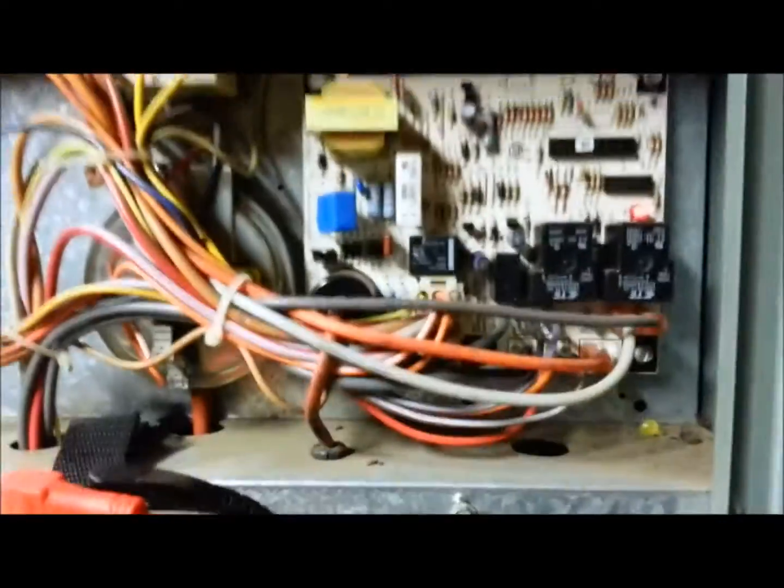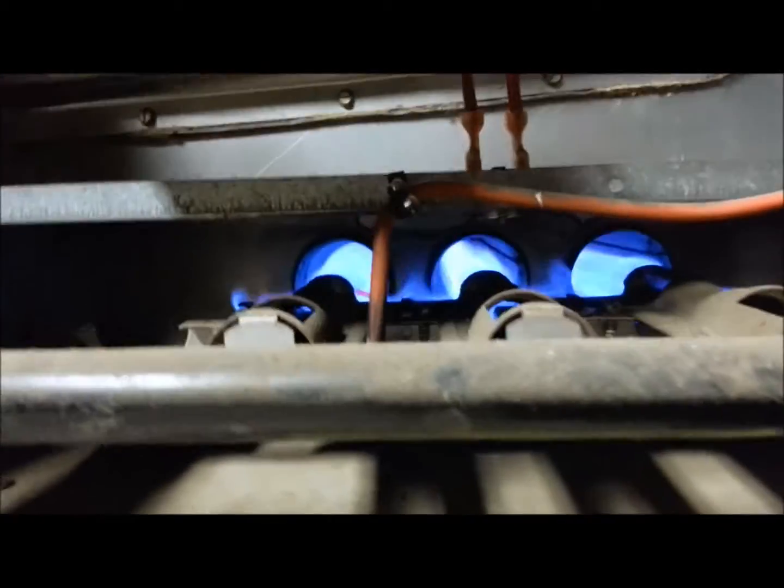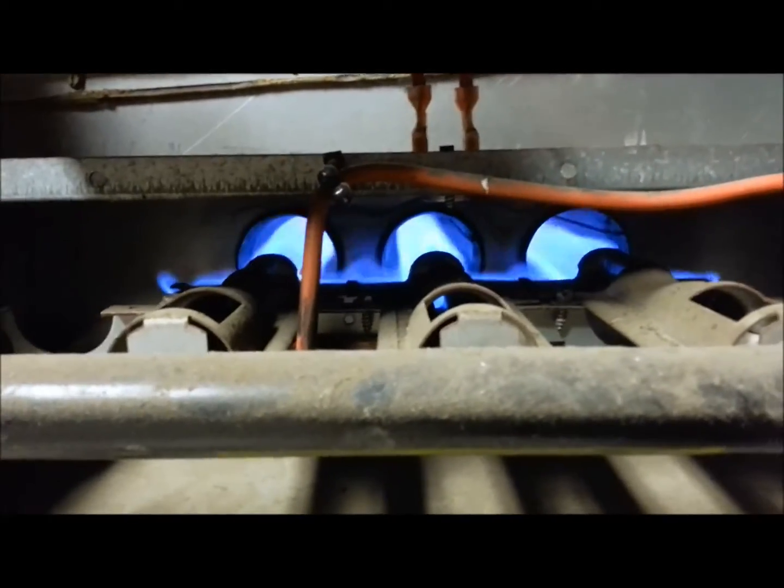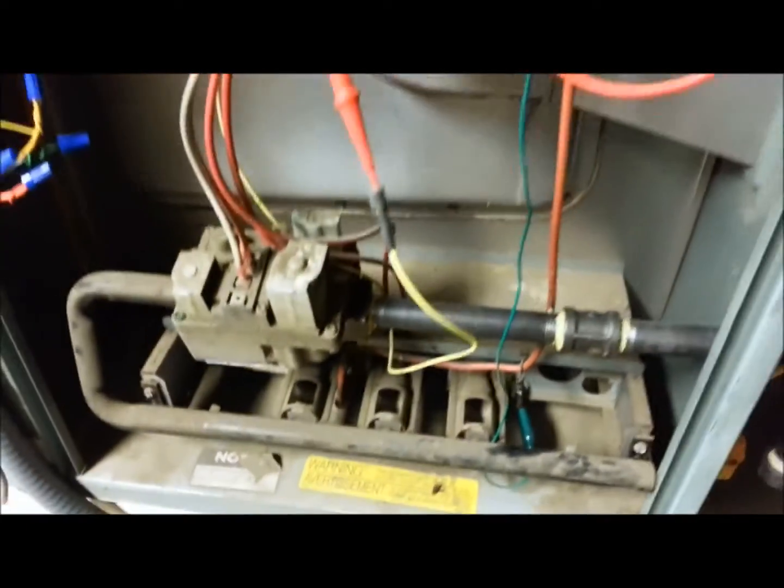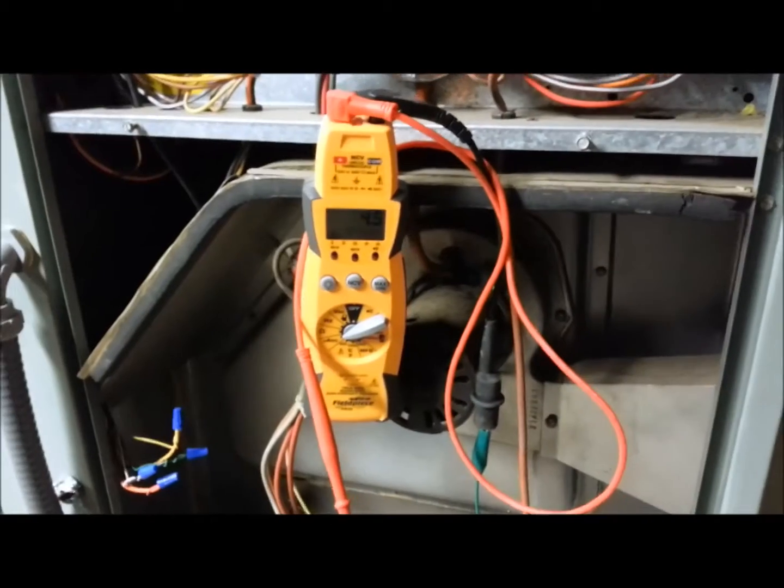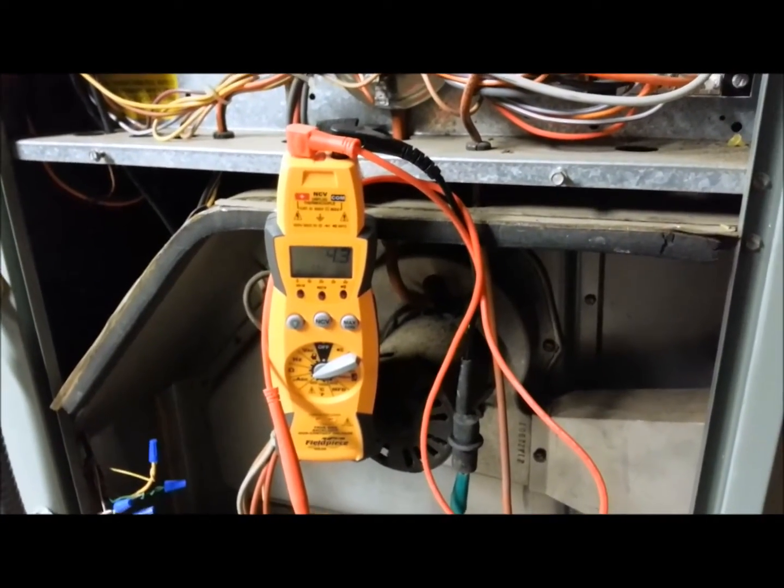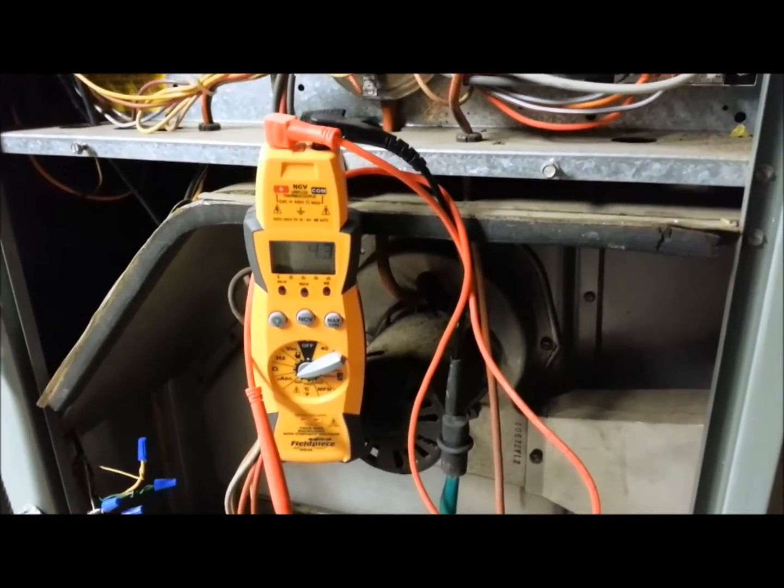And the blower come on. Let's be looking good. Look at our burners again, make sure that everything's clear. All right, clean flame sensor should work good, should last quite a while longer. Doesn't need to be replaced, just clean.